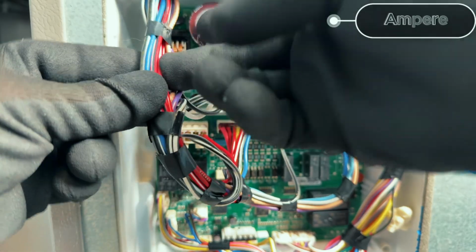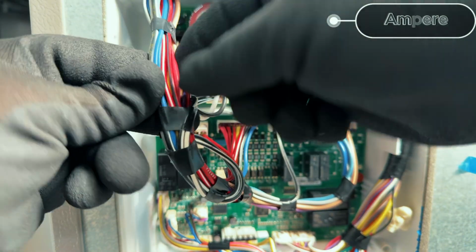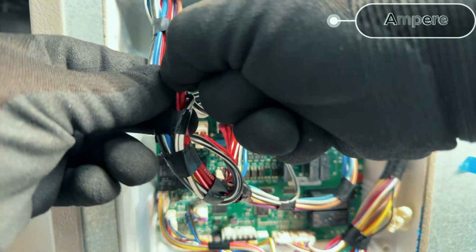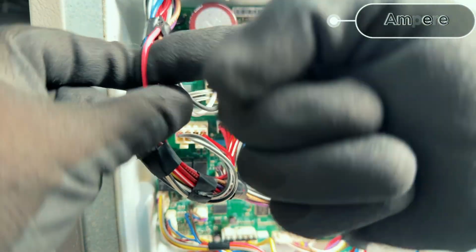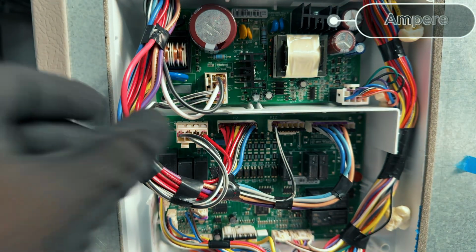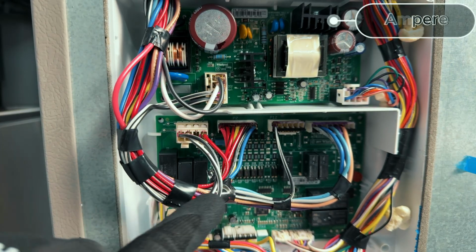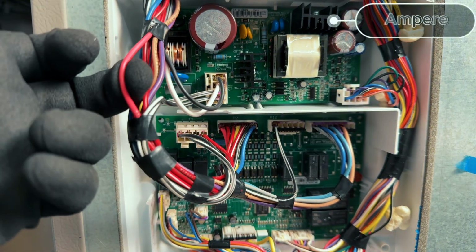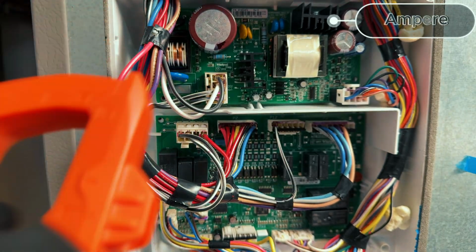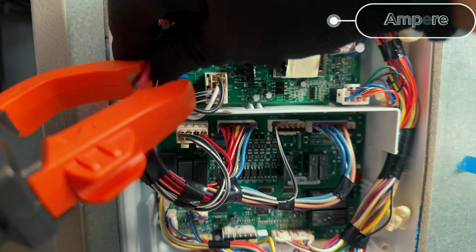So what I can do is I have some space right here. If I go through this harness here and find my defrost wire, what I can do is just pull it out enough to clamp it. And here it is. Let me isolate it. All right, now I have room right here. Doesn't mean I have to be at the connector. As long as I can find that wire anywhere else in the harness, I can check it somewhere else. And what we're going to be doing is using the clamp here to check it. So just to show you here, I'm going to clamp it around just that wire.